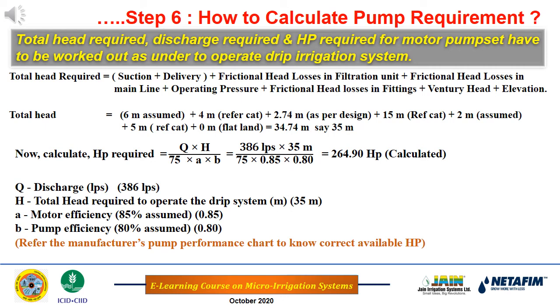In this design, suction plus delivery is assumed as 6 meter. Frictional head losses in filtration unit is 4 meter as per the catalog. Frictional head losses in main line is 2.74 as per the design. Operating pressure is taken as 15 meter as per the catalog. Frictional head losses in fittings is taken as 2 meter. Venturi head is taken as 5 meter as per the catalog. Elevation is 0. Total head is equal to 34.74 meter, say 35 meter.